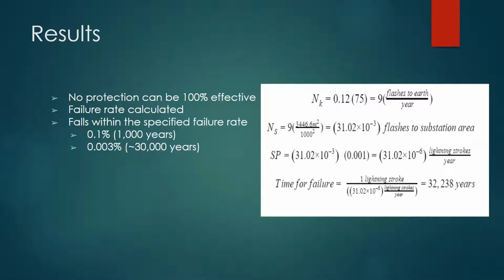So then, as a way to kind of judge how well we protected our substation, we did some calculations to determine the rate of failure. So no protection can be 100% effective. You can keep adding masts until you've got as many as you want, really, but it's never going to get the protection up to 100%. So you can see how we calculated our failure rate on the right. First, we determined the number of lightning strokes that would get to the ground per year for the Brookings area. Then we used that number to determine how many of those flashes would be within the area of our substation.